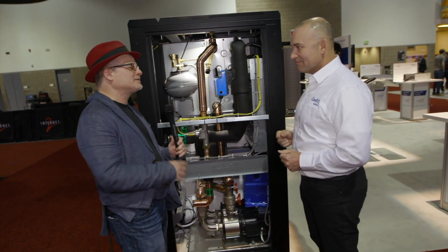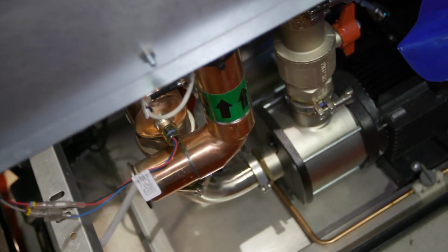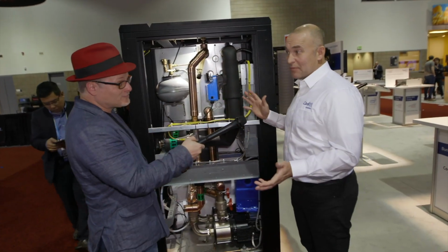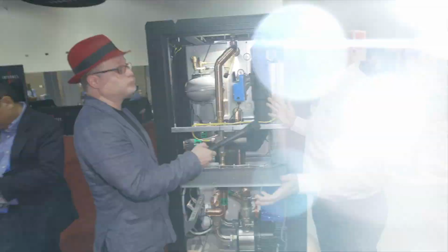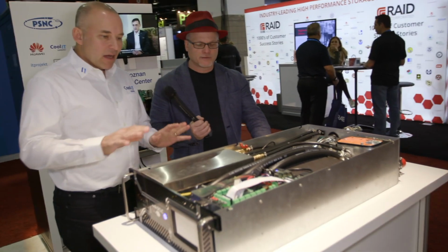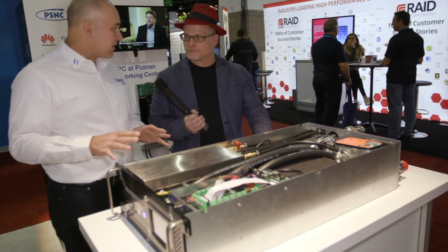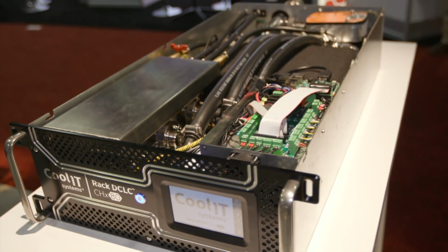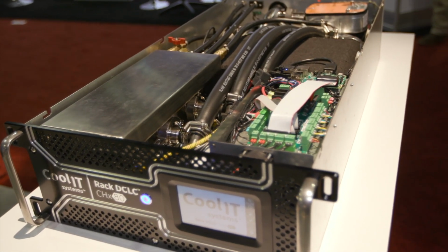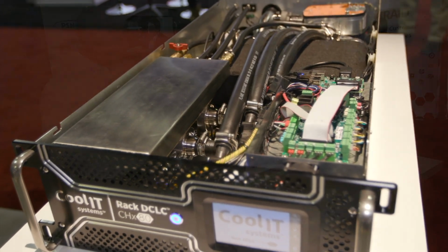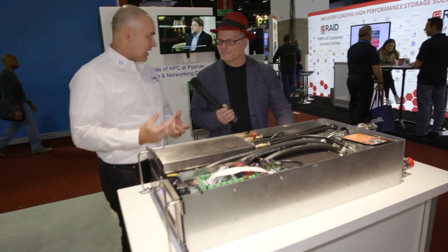How many kilowatts is that, roughly? Well, it depends on the kilowatt load in each node, but the capacity inside here is up to about 650 kilowatts. What do we got here, Jeff? This is our flagship in-rack CDU. We call it our CHX80. It has a heat capacity of about 80 kilowatts, and that's 80 kilowatts of just the liquid absorbed heat.